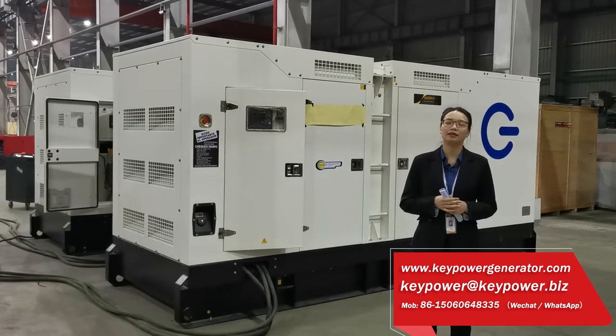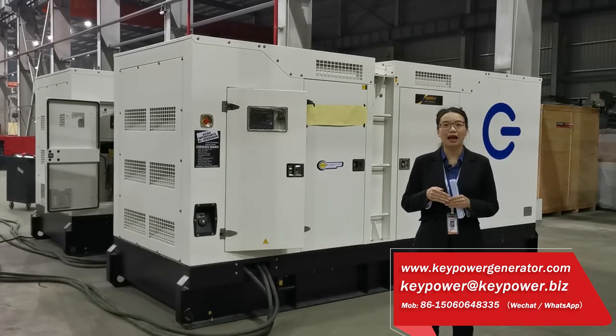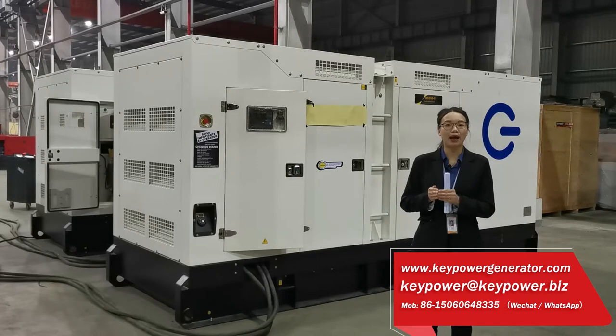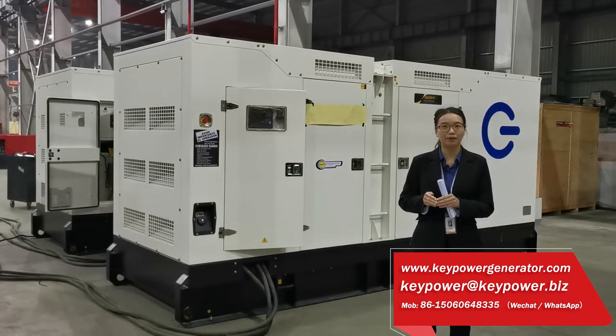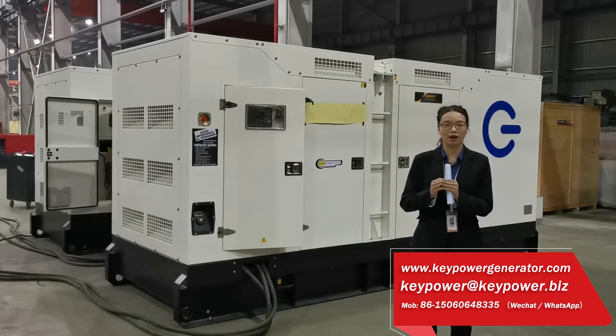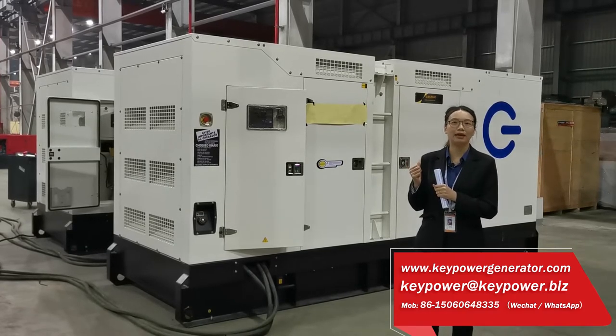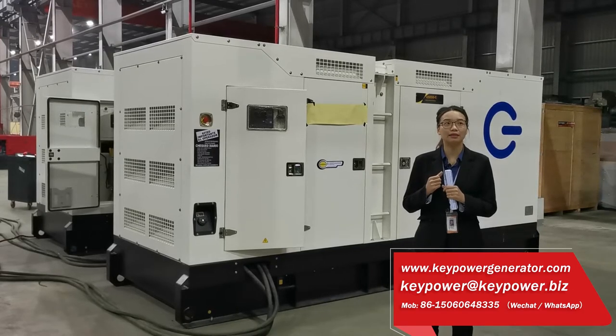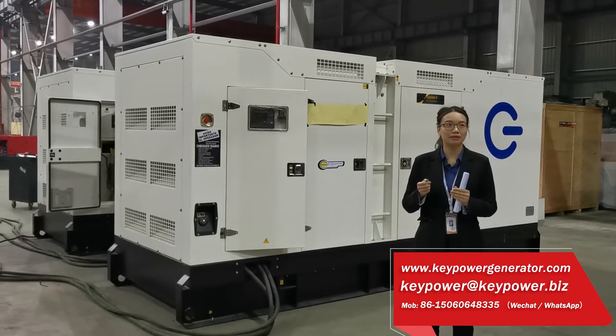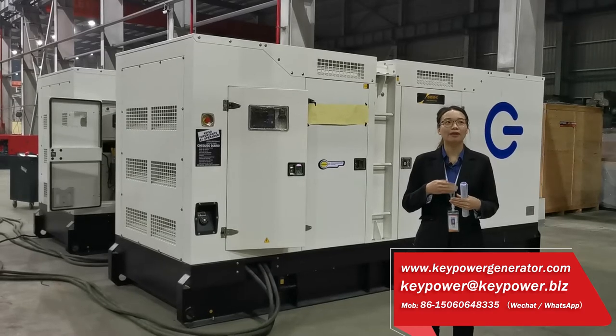For example, if one generator is 500 kVA and the other one is 300 kVA, the total power is 800 kVA. If the load is only 600 kVA, 600 kVA occupies 75% of the 800 kVA. The output of each generator will be only 75% of its rated power. For the 500 kVA, the power output is around 375 kVA. For the 300 kVA generator, 75% of rated power is 225 kVA. This is their function. They can share the load at the same rate.